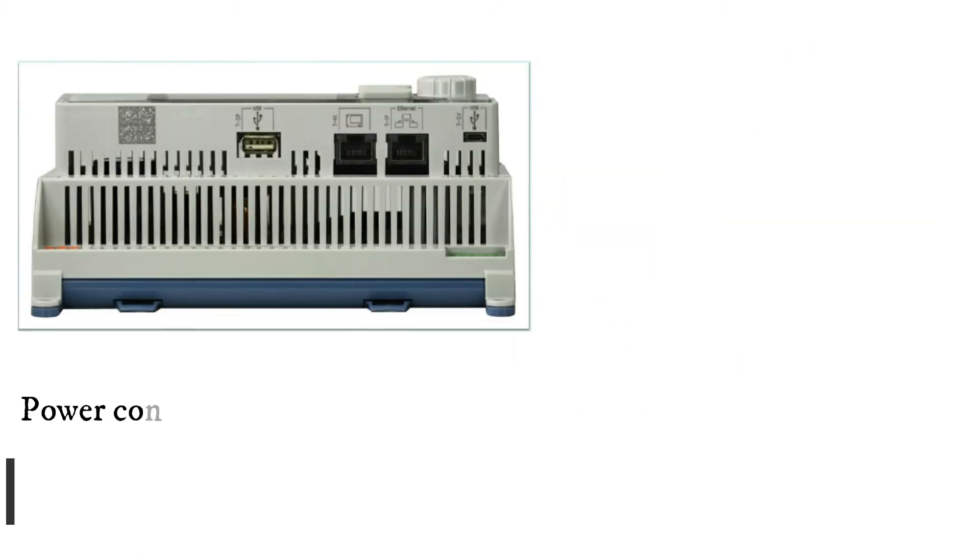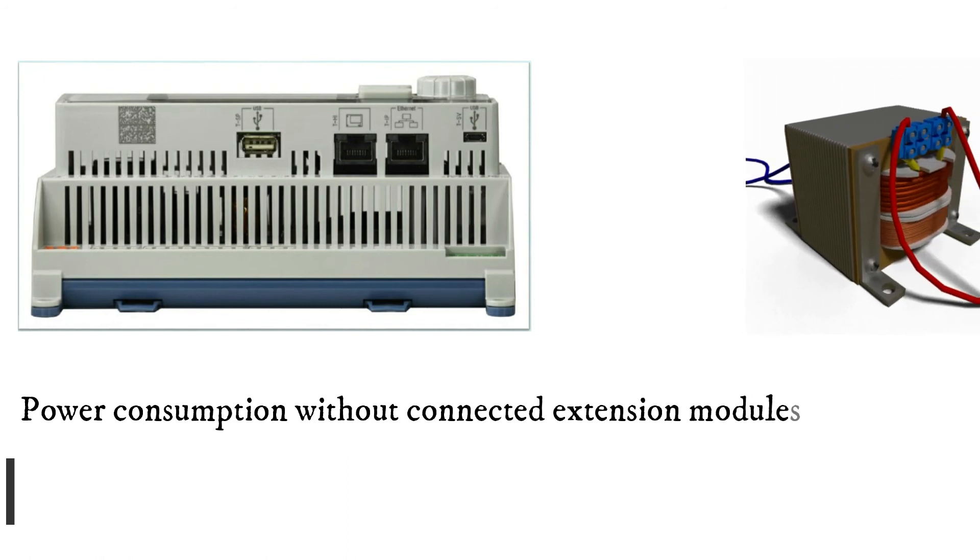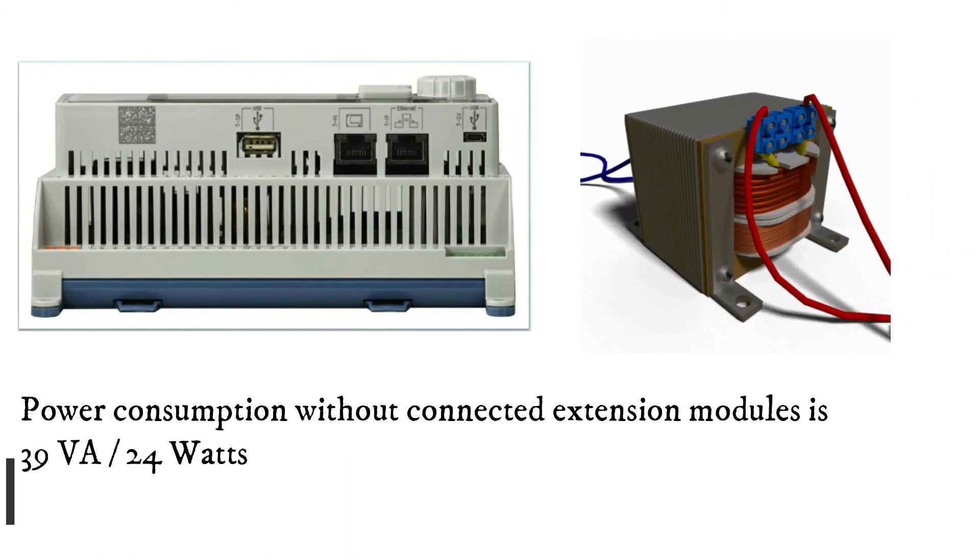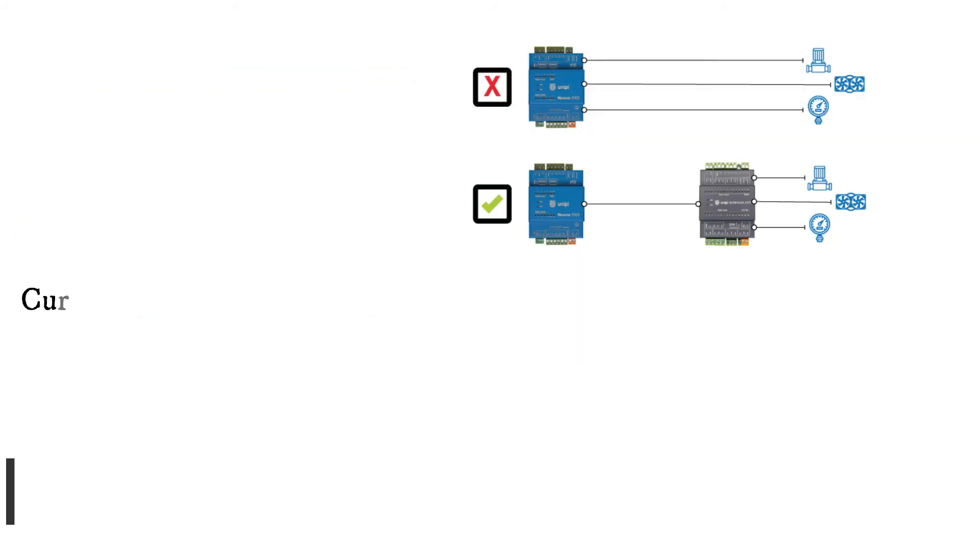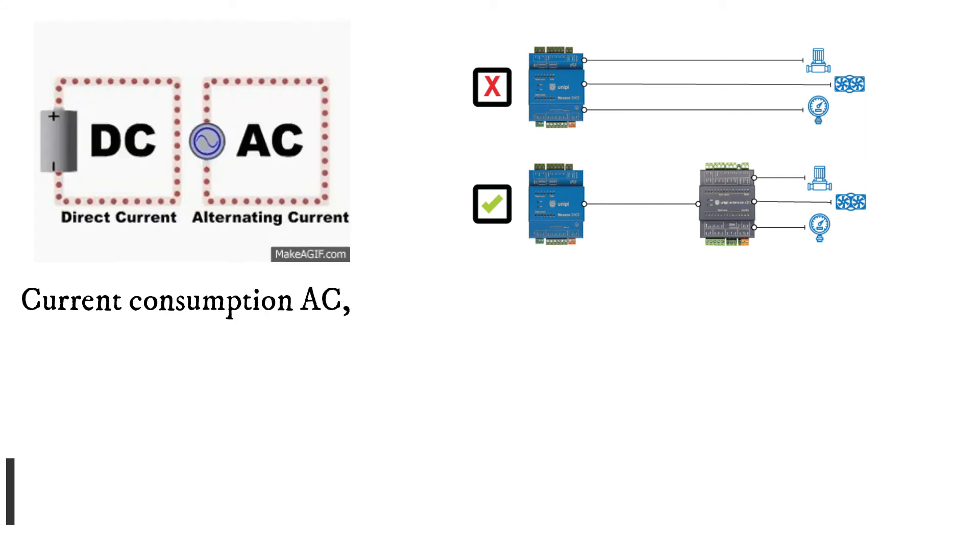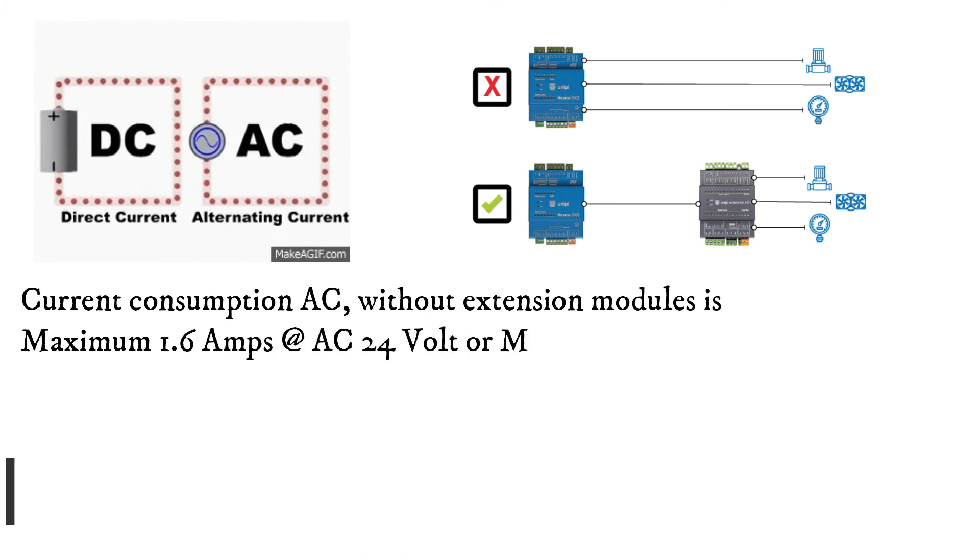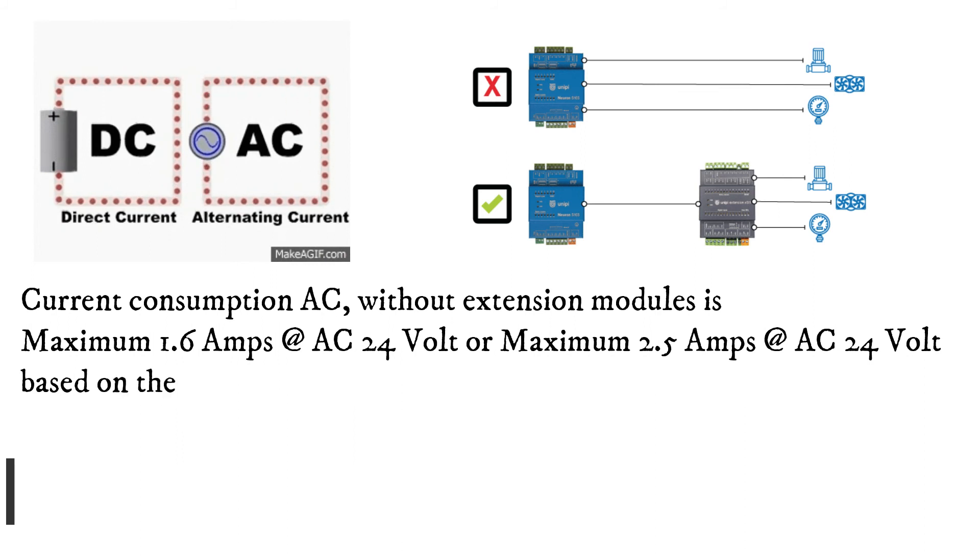Power consumption without connected extension modules: 39VA, 24W or 60VA, 43W based on the model. Current consumption AC without extension modules: Maximum 1.6A at AC 24V or maximum 2.5A at AC 24V based on the model.